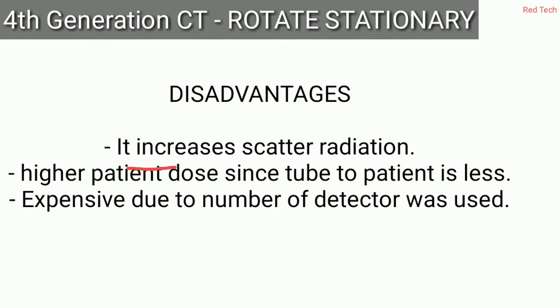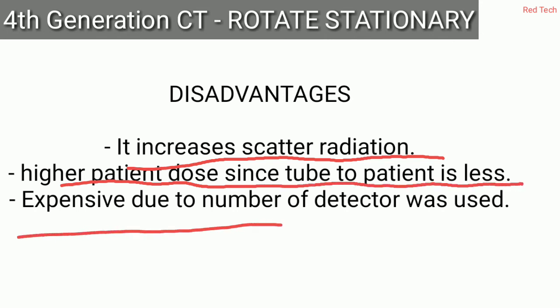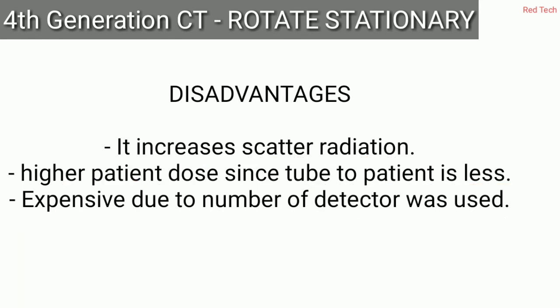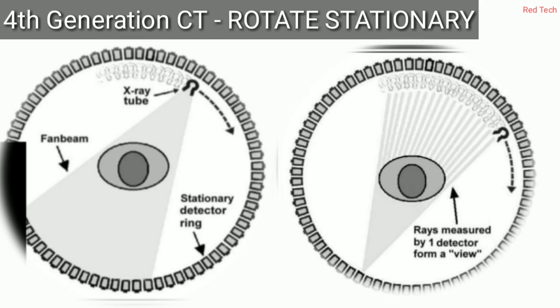Looking at the disadvantages: it increases scatter radiation, since increasing the number of detectors also increases scatter. There is higher patient dose because the tube-to-patient distance is less. It is also expensive due to the large number of detectors used — this is common sense, as more detectors make the CT machine more costly.